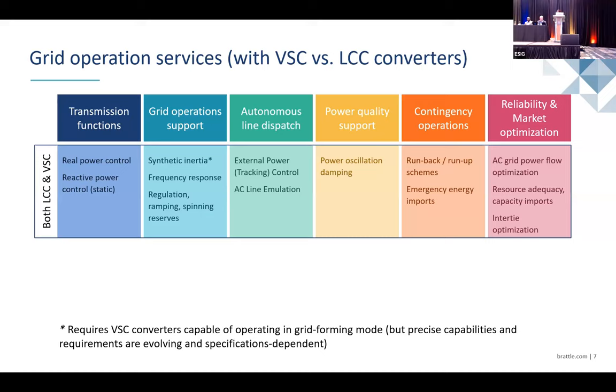And similarly, based on the events happening in the power system, HVDC can automatically adjust its power flow. For example, if one line is lost in the grid, it can see that a line is lost and automatically ramp down its power. And when the line is back, it can automatically increase the power flow into the grid. Basically, it can do run back, run up, and energy import and export based on the events happening in the power system. This HVDC can also be used for grid reliability and market optimization, basically.